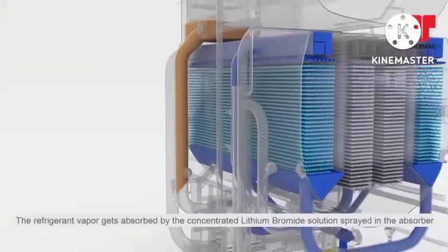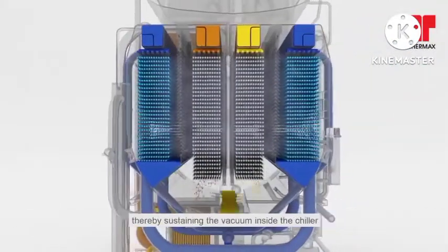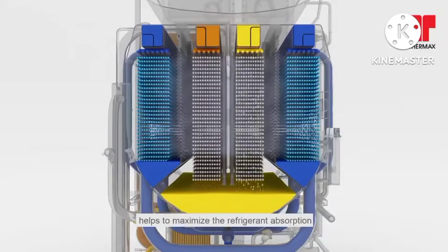The refrigerant vapor gets absorbed by the concentrated lithium bromide solution sprayed in the absorber, thereby sustaining the vacuum inside the chiller.